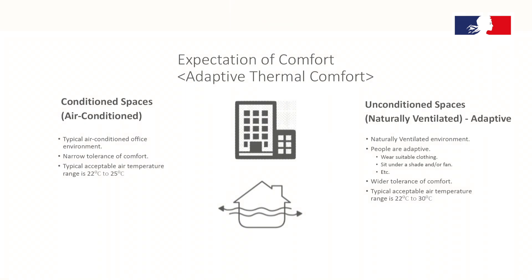Depending on the space type, we have an expectation of comfort. If we are sitting in an office environment, we expect an air-conditioned environment of 22 to 25 degrees Celsius. If we are sitting in a naturally ventilated space, our expectation of thermal comfort increases up to 29 to 30 degrees Celsius.